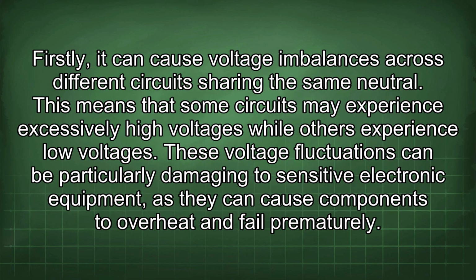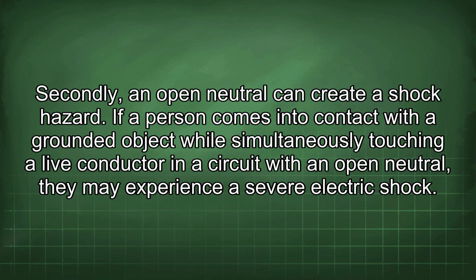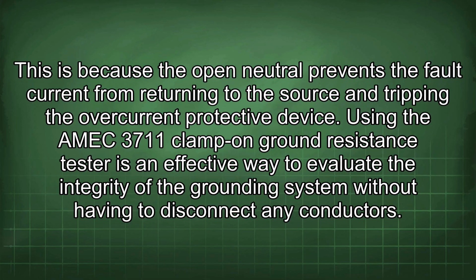Firstly, it can cause voltage imbalances across different circuits sharing the same neutral. This means that some circuits may experience excessively high voltages while others experience low voltages. These voltage fluctuations can be particularly damaging to sensitive electronic equipment, as they can cause components to overheat and fail prematurely. Secondly, an open neutral can create a shock hazard. If a person comes into contact with a grounded object while simultaneously touching a live conductor in a circuit with an open neutral, they may experience a severe electric shock. This is because the open neutral prevents the fault current from returning to the source and tripping the overcurrent protective device.